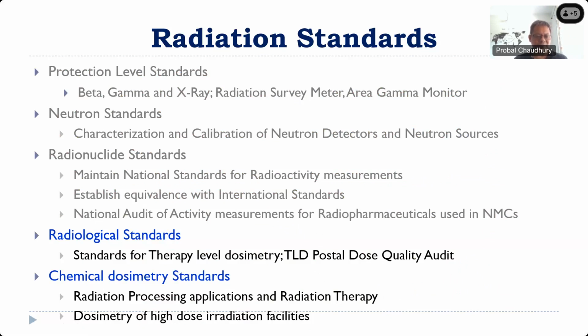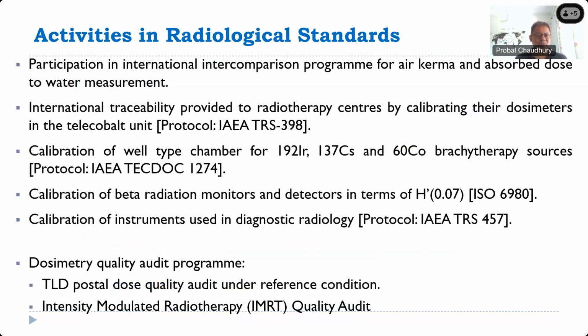They have the standards for therapy level dosimetry, wherever therapy dosimetry is used, and a thermoluminescence dosimetry postal quality audit. The group also participates in international intercomparison programs for air kerma and absorbed dose to water measurement, and provides international traceability to radiotherapy centers by calibrating their dosimeters in the telecobalt unit. This is as per the IAEA TRS 398 protocol. Then calibration of well type chambers for iridium 192, cesium 137, and cobalt 60 brachytherapy sources.